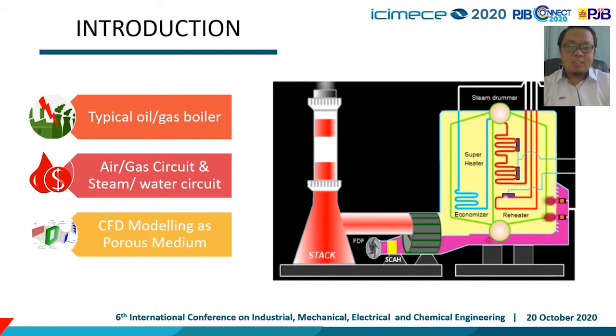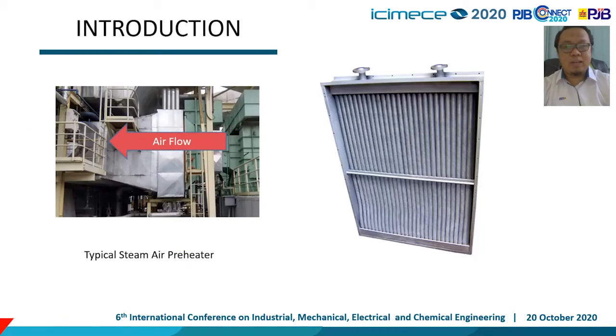medium. The steam coil air preheater will raise the air temperature before it enters the main air heater here, and it will prevent the sulfur condensation in the hot gas side of the main air heater that can corrode the element of the air heater.